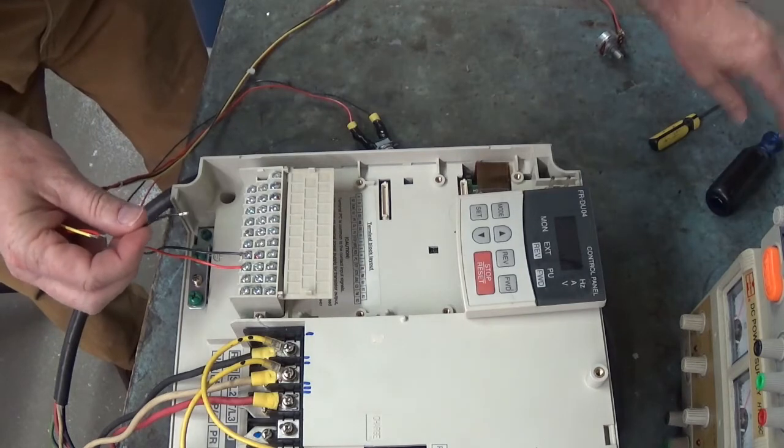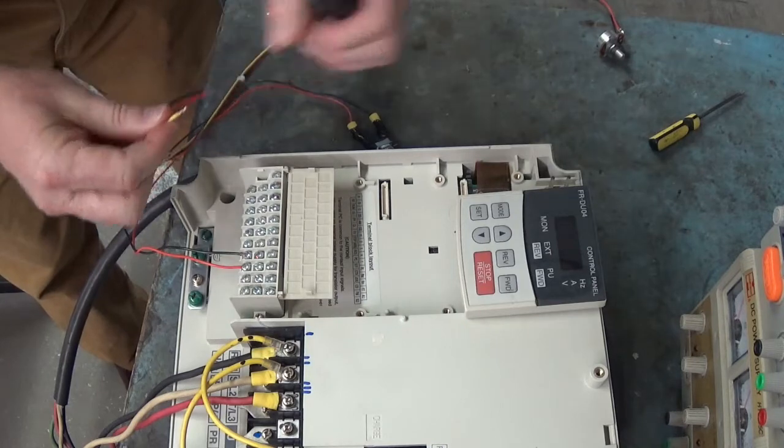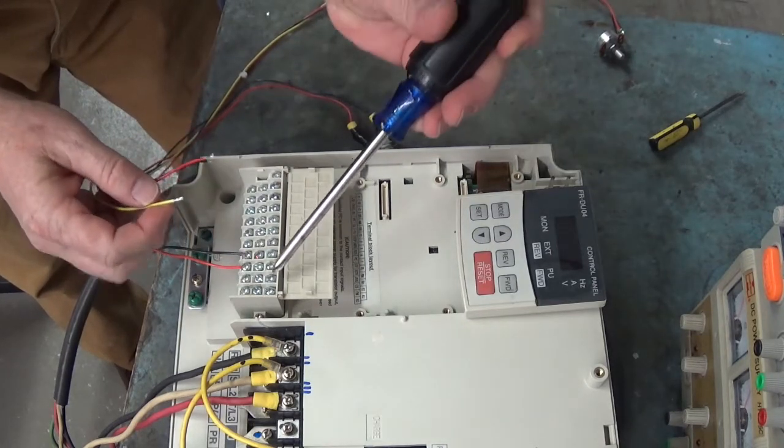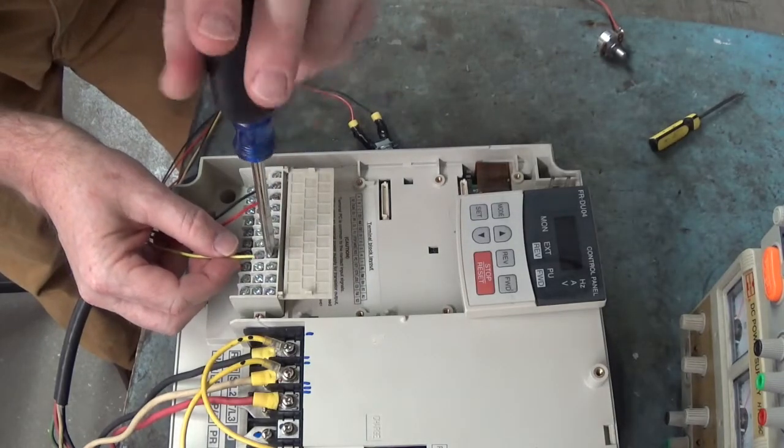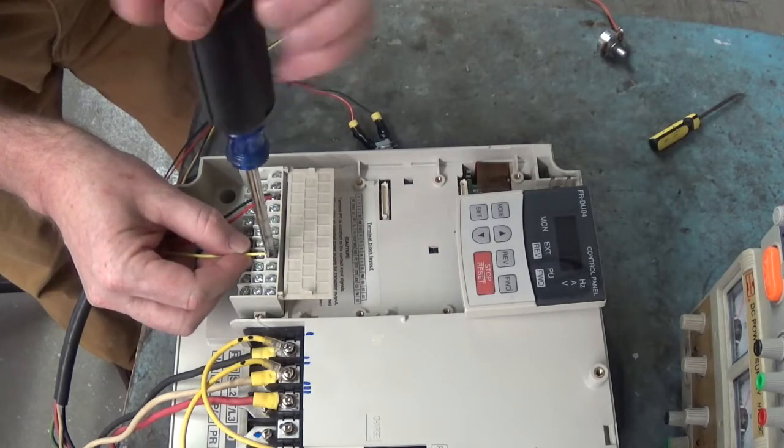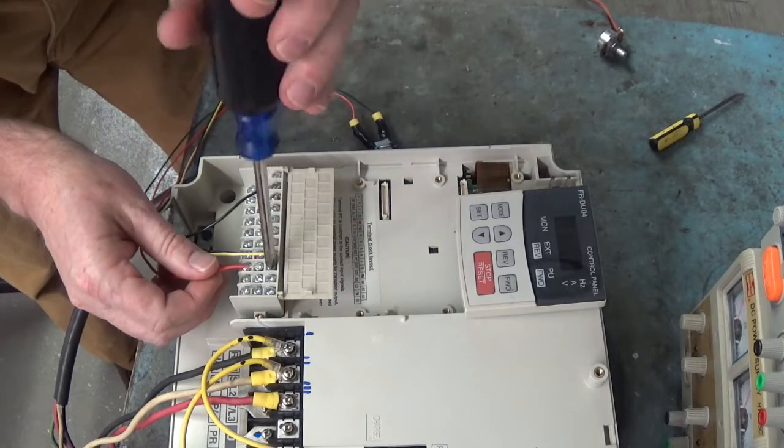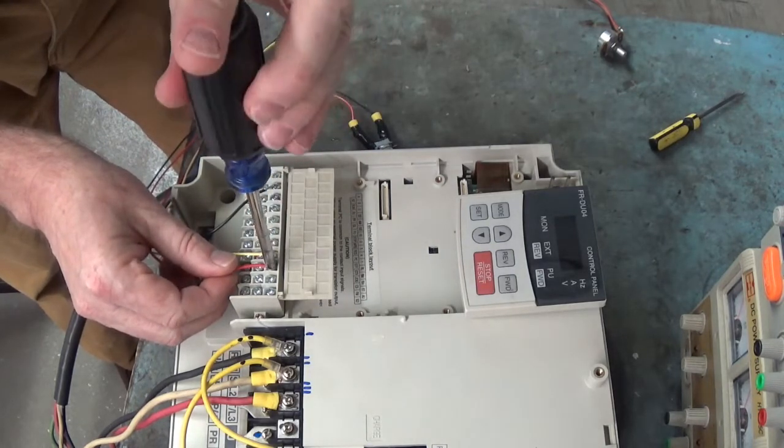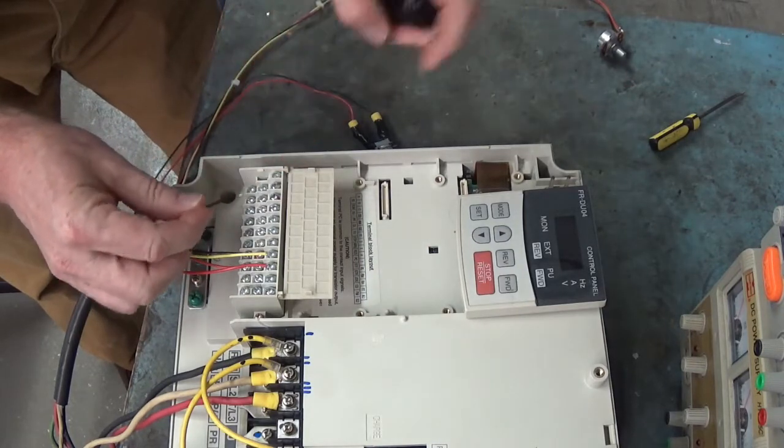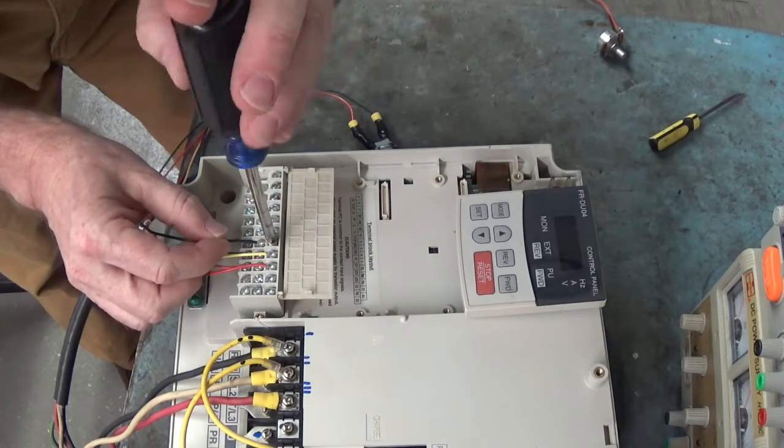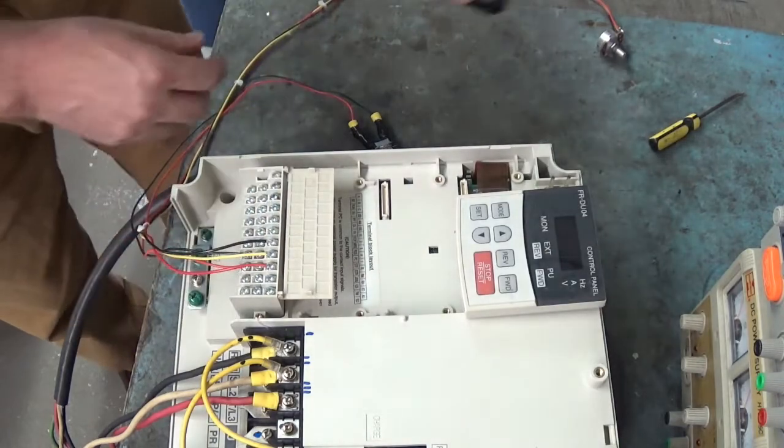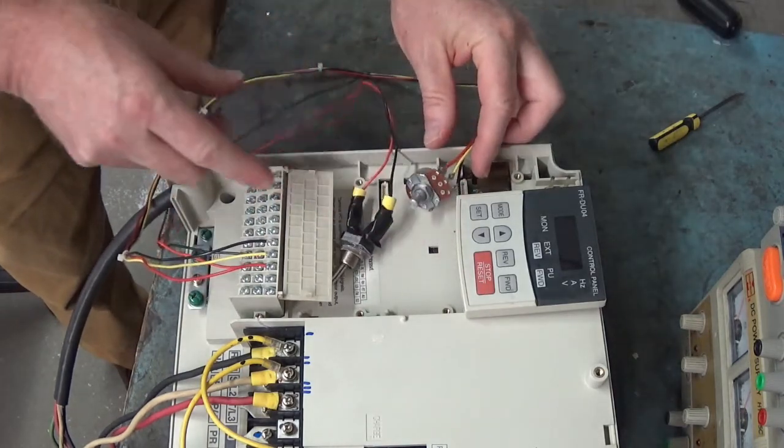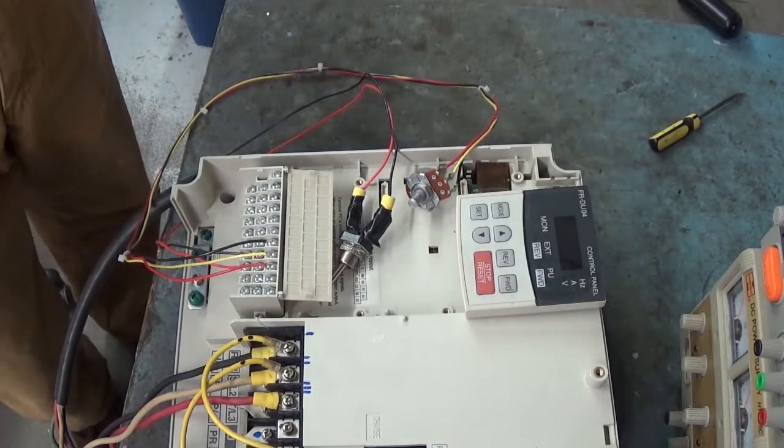Now the speed reference goes to terminals 5, 2, and 10 on the top row. There we go. The wiper goes to 2, and the wings of the potentiometer go to 5 and 10. There we go. That's all you need to get this drive to run. Let's go power it up, see what it does.